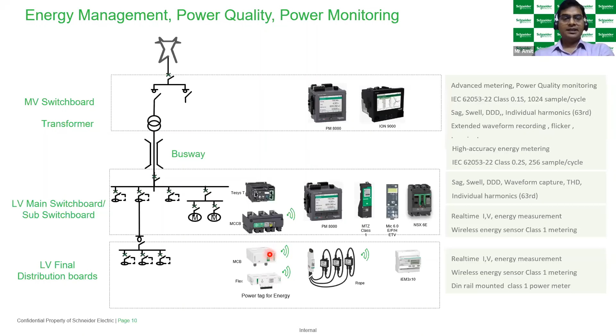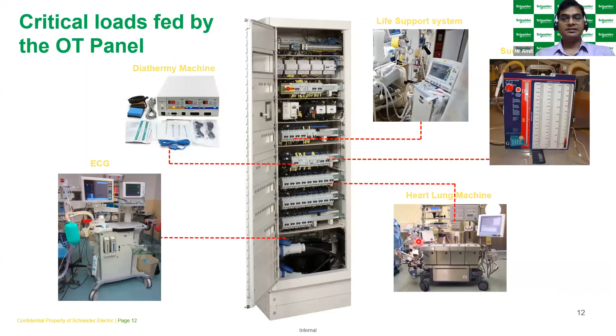In the OT panel, we got to know that in all hospitals, in all the OTs, the top priorities are power reliability, system redundancy, earth leakage, and electrical shock. All the OTs are supplying diathermy machines, ECG, heart lung machines, suction machines, and protecting the human being. As per the IEC guideline across the globe, there is a mandate, IEC 60364-7-710, that near the patient you need to change your earthing system from TN-S to IT earthing system, and we are basically talking about an isolation transformer.